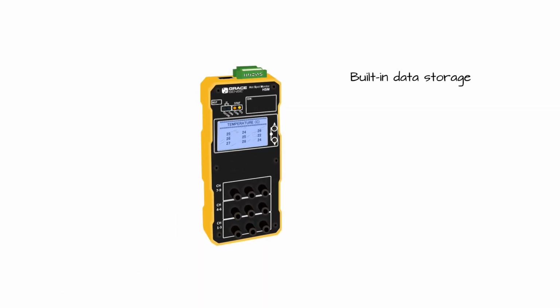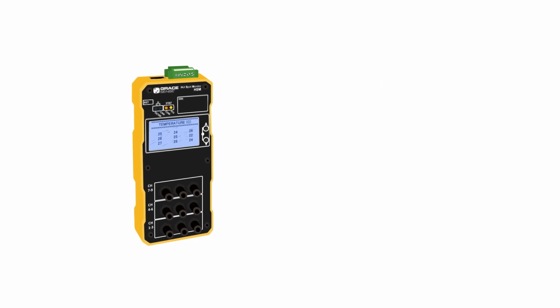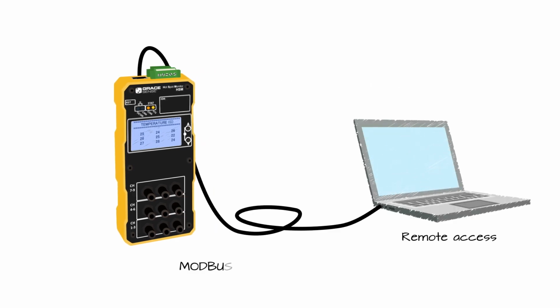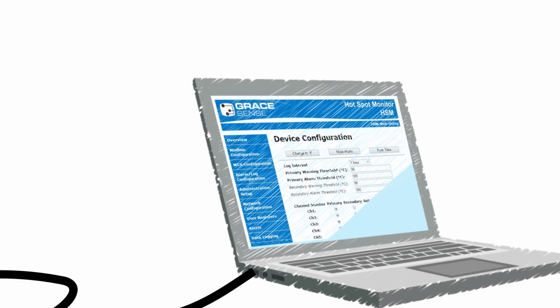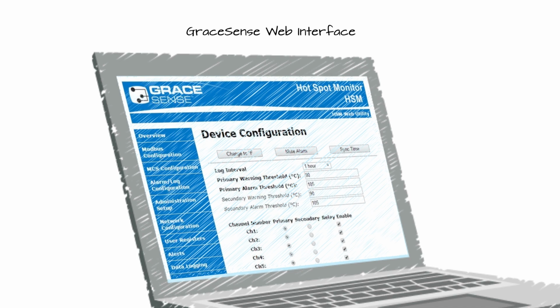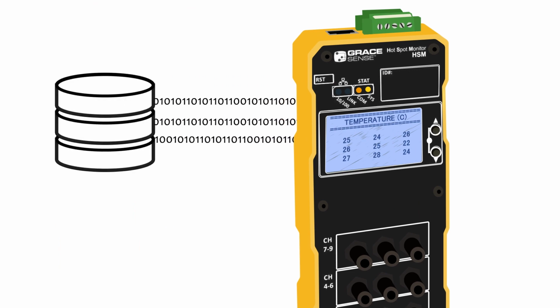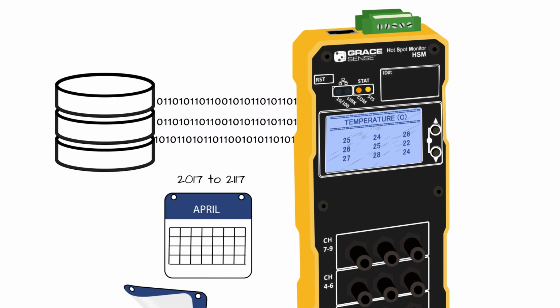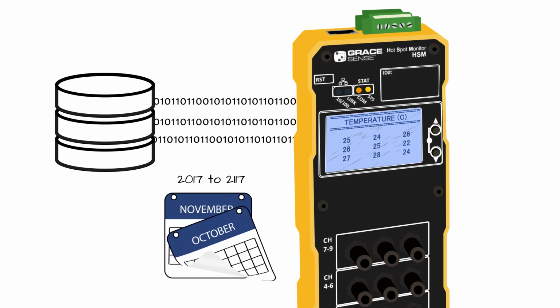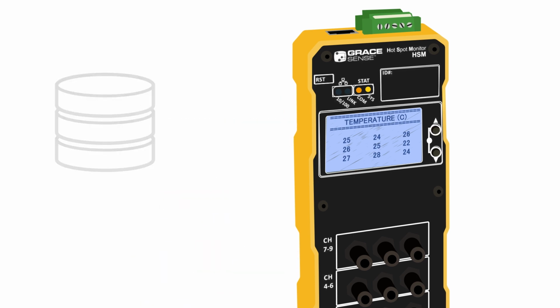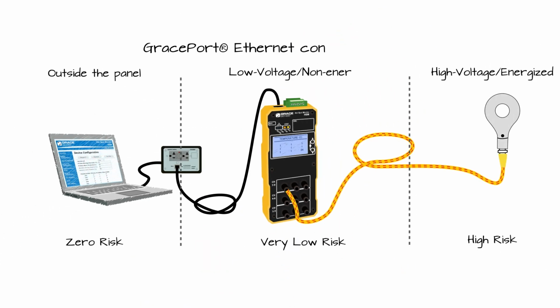The Hotspot Monitor comes with 16 megabytes of built-in memory for data storage. By connecting the GraceSense HSM module via Modbus TCP/IP or Ethernet IP and accessing the web utility tool, users can configure the temperature thresholds, time intervals, and relay outputs. This tool further enables access to the real-time data logs and downloads the stored data for analysis and trending, connecting directly to the device or safely through closed doors using a GracePort Ethernet connector interface.